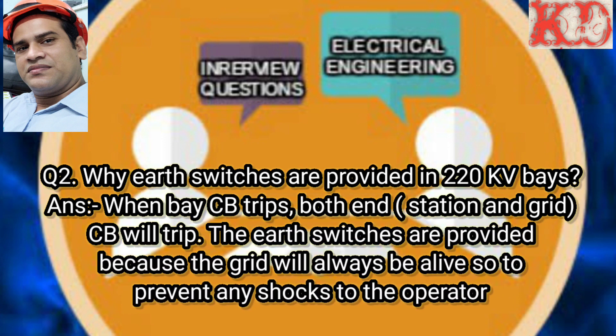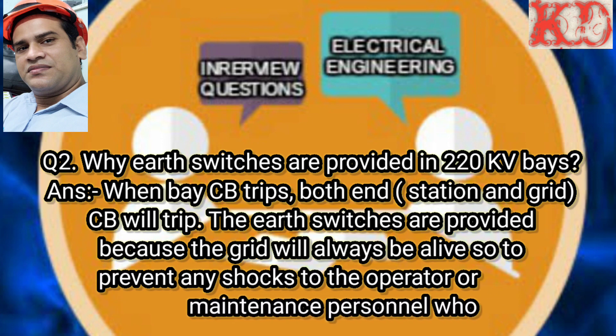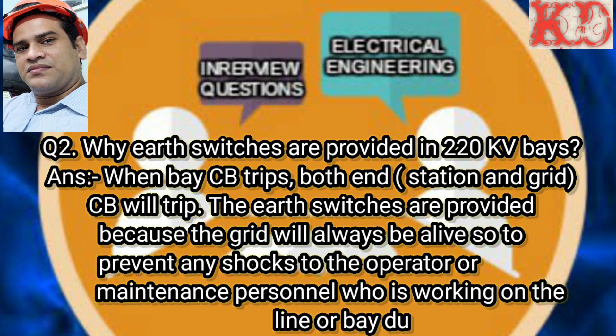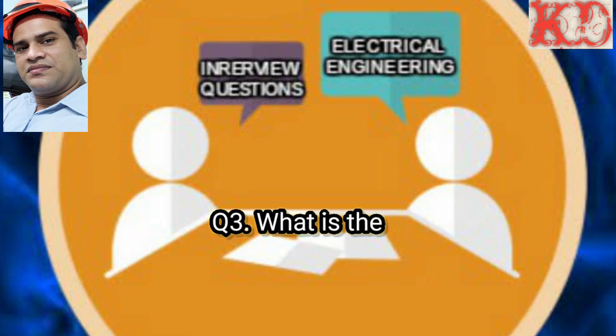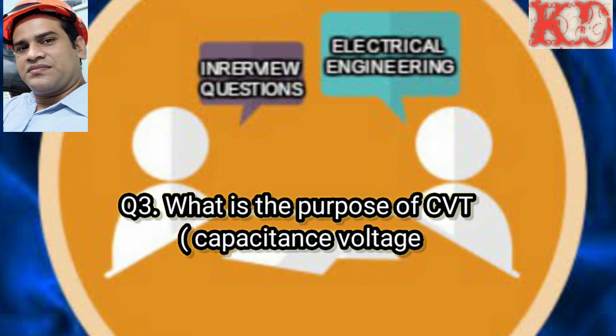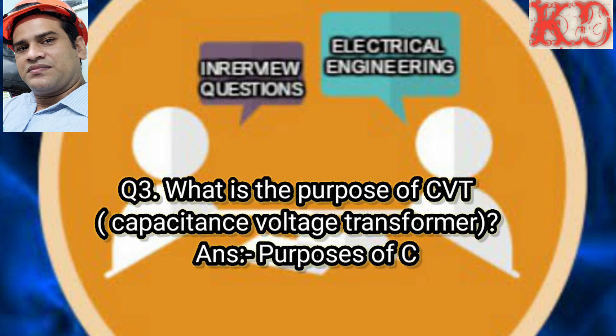Question number 2: Why are earth switches provided in 220 KV? Answer: When a bay CB trips at both ends, the station and grid CB will trip. Earth switches are provided because the grid will always be alive, to prevent any shock to the operator or maintenance personnel working on the line, or to prevent accidental energizing of the bus.